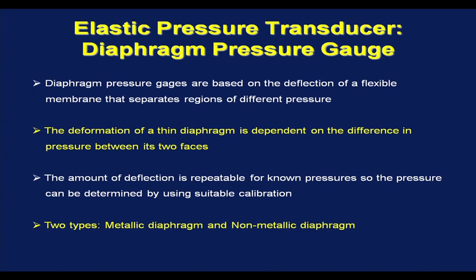Next, let us talk about another elastic pressure transducer, the diaphragm pressure gauge. Diaphragm pressure gauges are based on the deflection of a flexible membrane that separates regions of different pressure. So, diaphragms are nothing but a flexible membrane. It can be made of metal, it can be made of non-metal as well. The deformation of a thin diaphragm is dependent on the difference in pressure between its two faces.